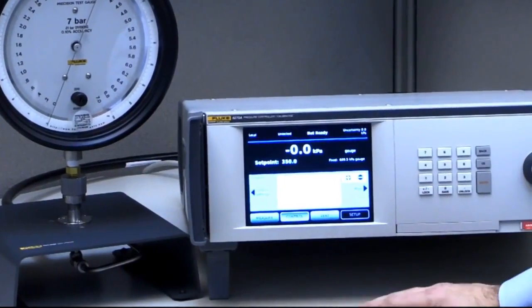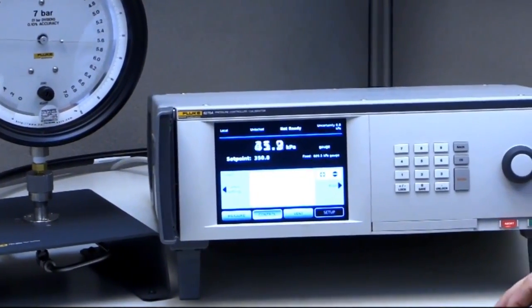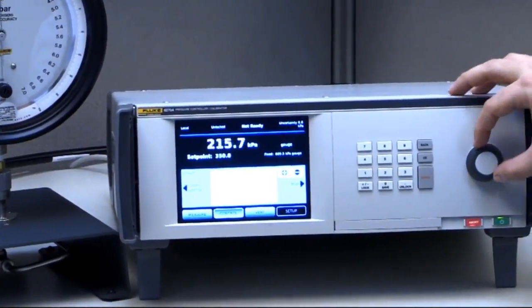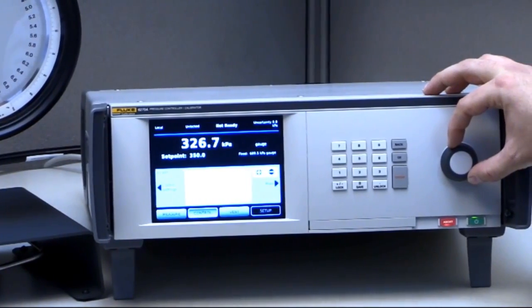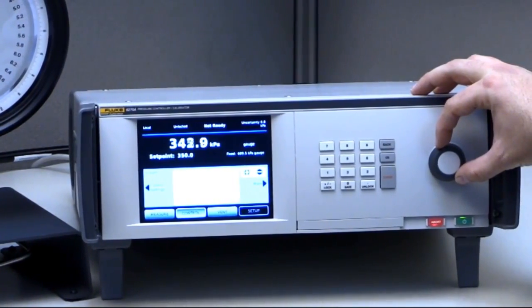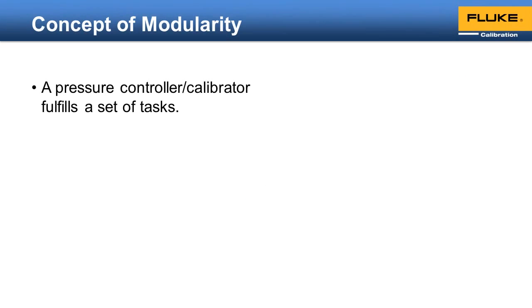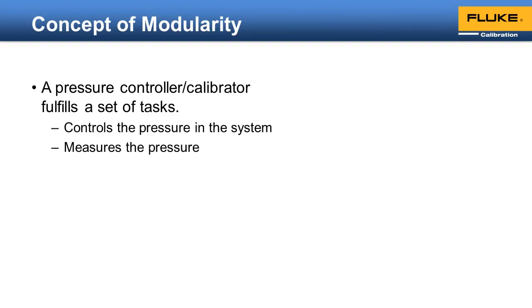Pressure controller calibrators are powerful tools for performing automated, efficient pressure calibrations. The term modularity is commonly used to describe these instruments. But what exactly does modularity mean, and how does modularity benefit the operator? A pressure controller calibrator fulfills a specific set of tasks. It controls the pressure in the system and actively measures that pressure. It may do this over a very tight pressure range or a very wide pressure range.